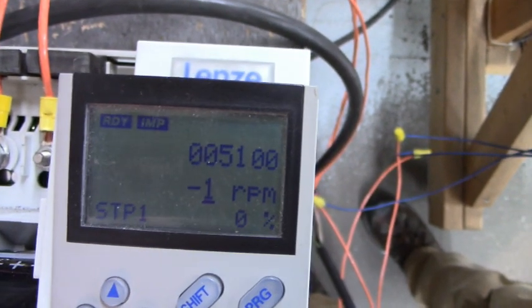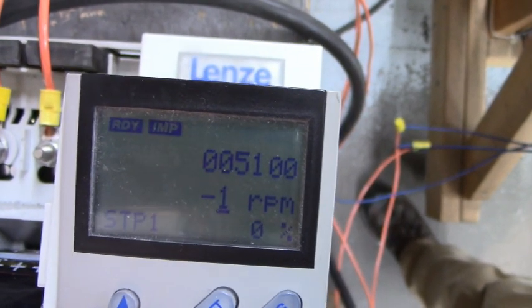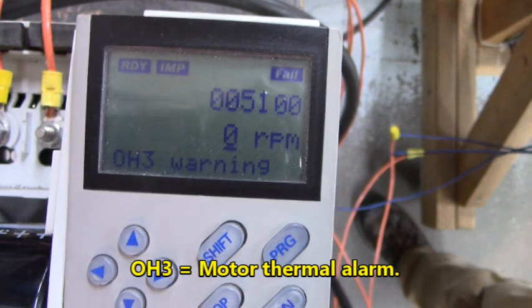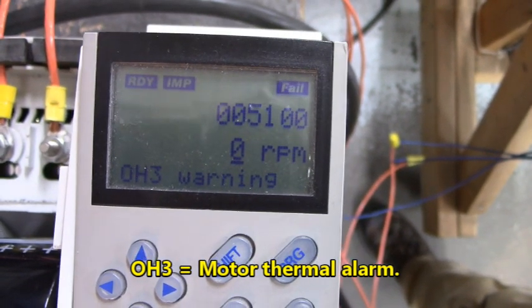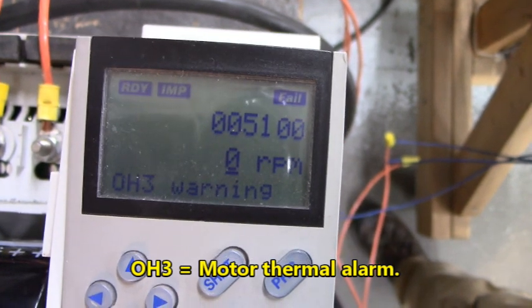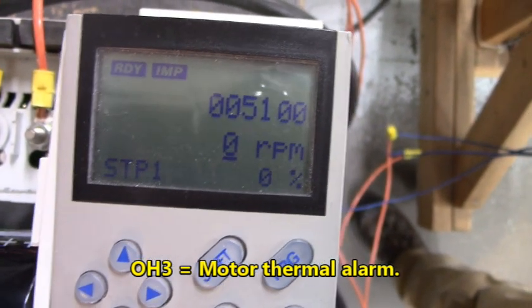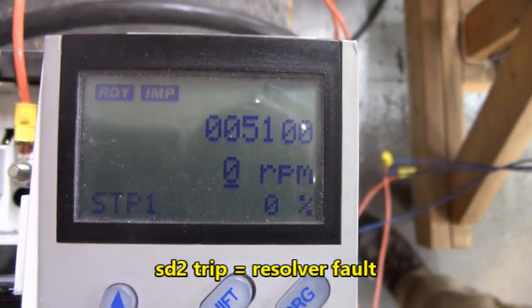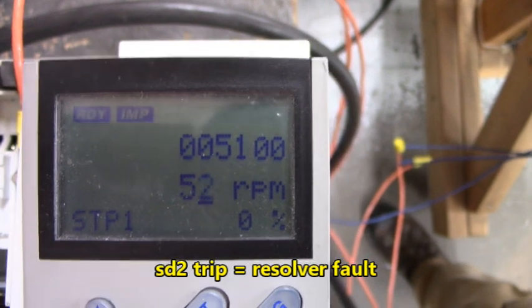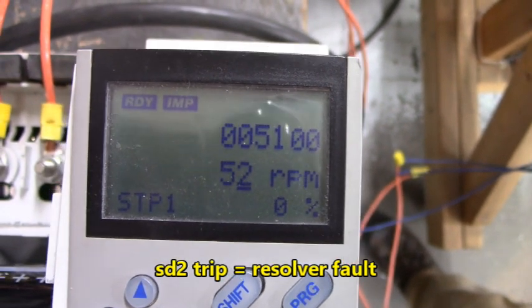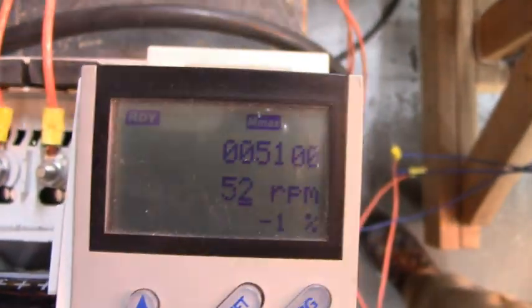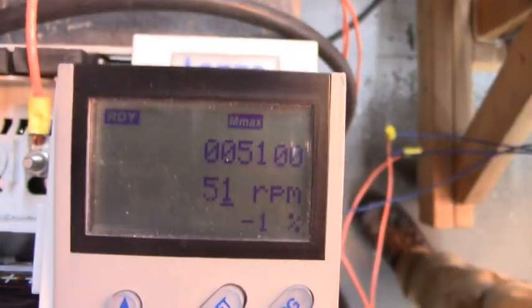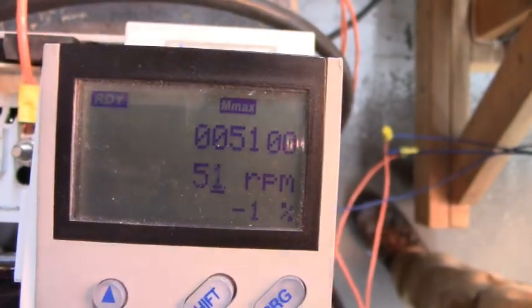Now, let me disconnect that motor thermal. By disconnecting the resolver feedback connector. There's OH3. A warning. Let me plug that back in. STP1. I'm going to rotate the DC motor and the resolver. And I'm going to enable the drive to run. Applying 24 volts to terminal 28. And 39. Ground.